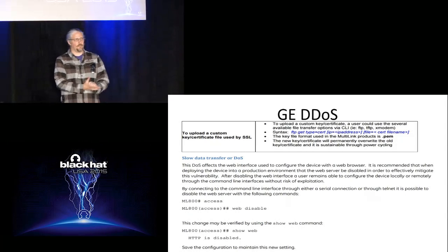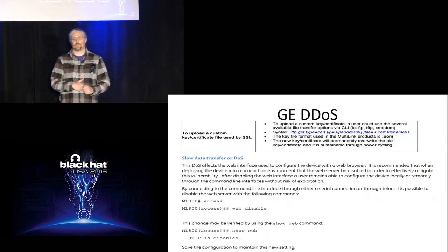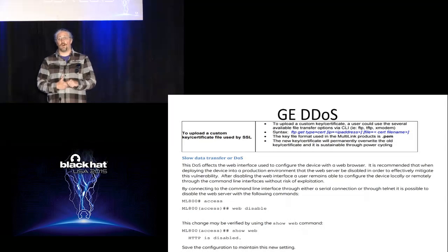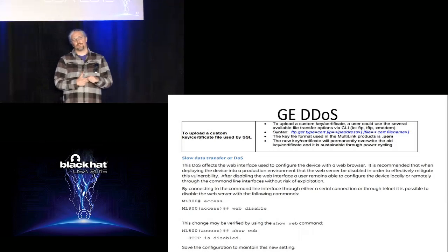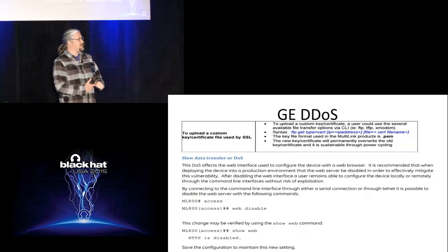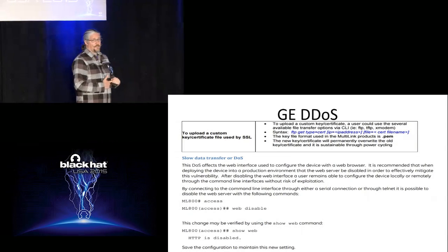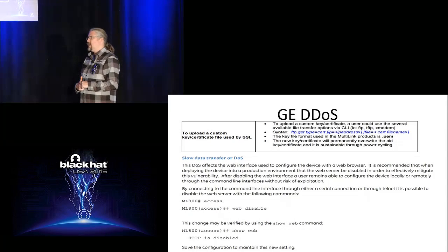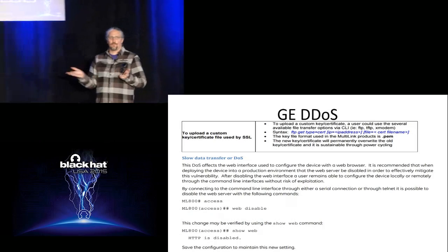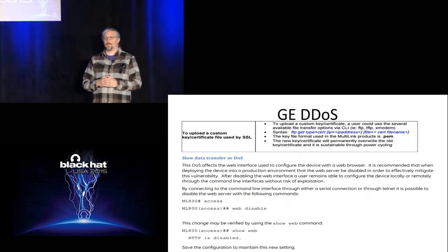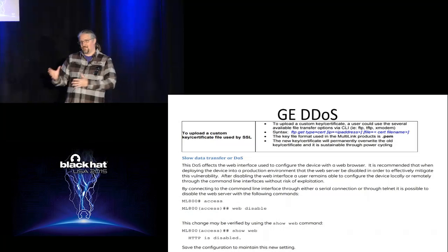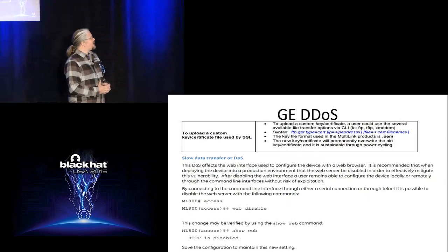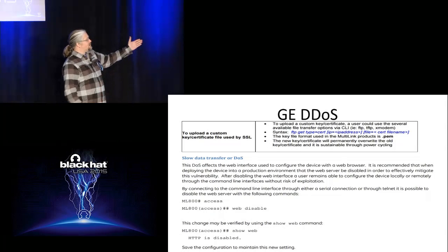One, this is a network device, and the DOS is not just for the web server, right? Essentially, if you DOS the web server of this device, the entire device reboots. So all traffic on this network will drop for 2 to 3 minutes while the device reboots from this DOS. Now, I don't know about you, but I find that pretty disturbing, right? Particularly when you're talking about a process control network. Imagine this was an H2S system and the alarms were polling across the network and there was some sort of a leak. Then during the time that you're DOSing the switch, you can't receive your safety messages telling you that there's an H2S leak.